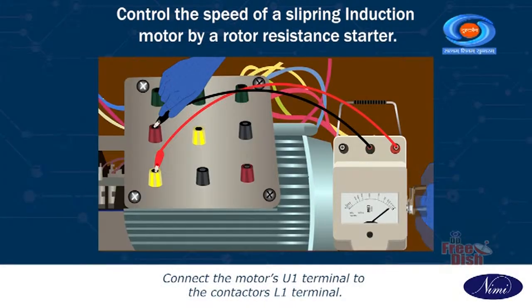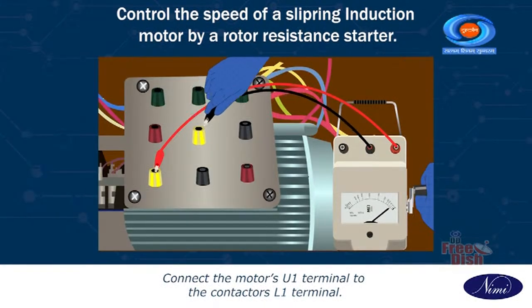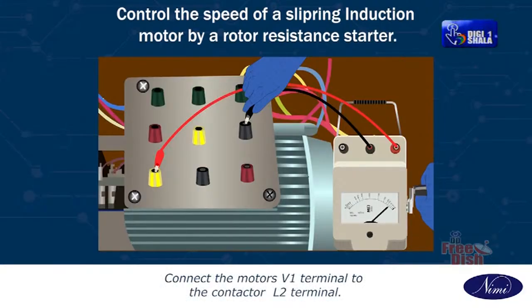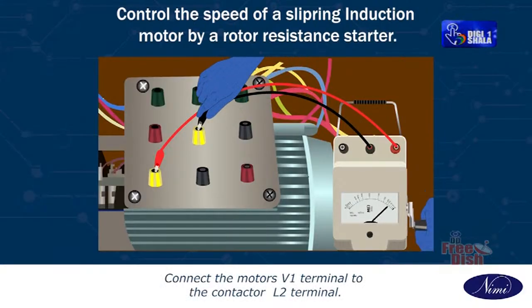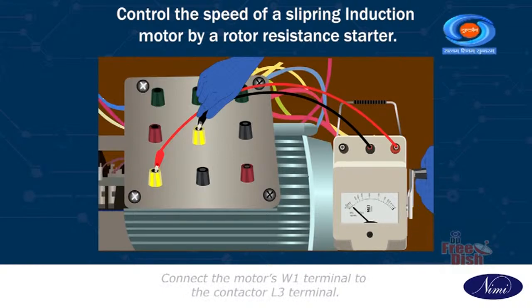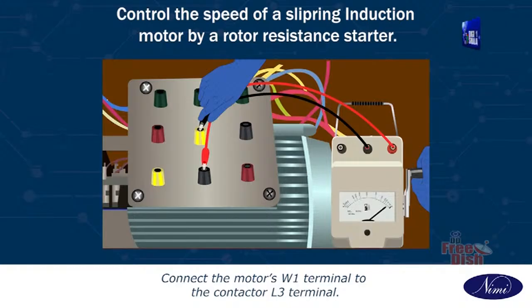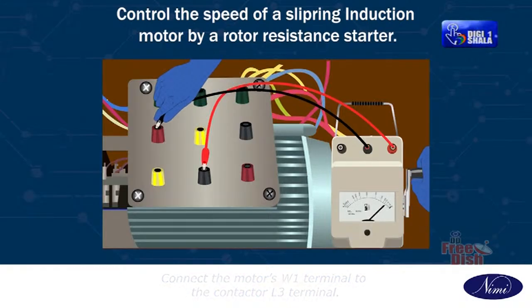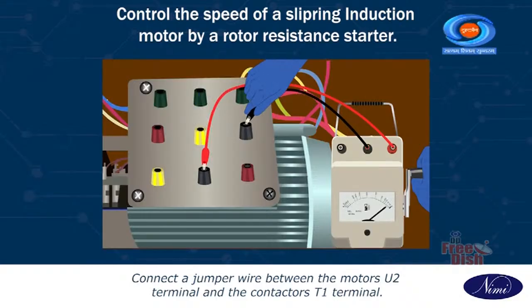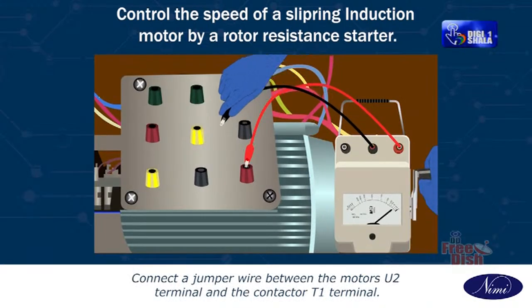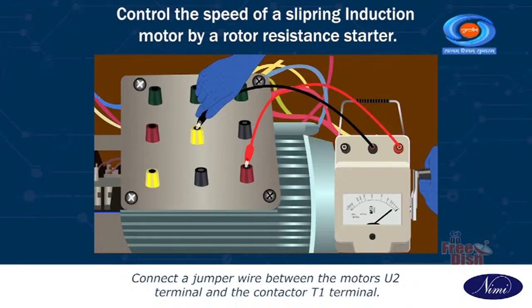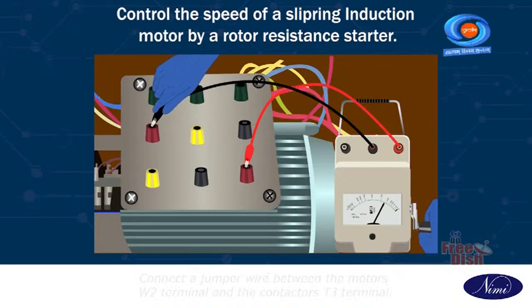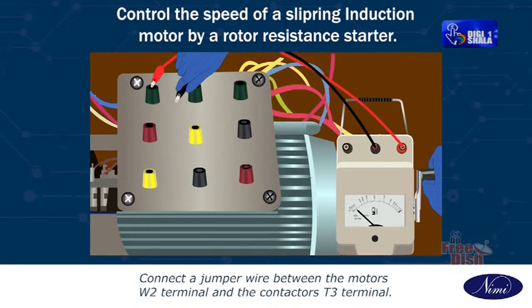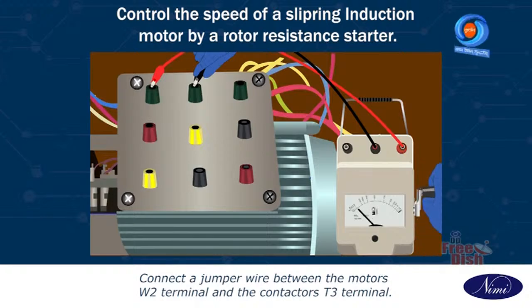Connect the motor's U1 terminal to the contactor's L1 terminal. Connect the motor's V1 terminal to the contactor's L2 terminal. Connect the motor's W1 terminal to the contactor's L3 terminal. Connect a jumper wire between the motor's U2 terminal and the contactor's T1 terminal. Connect a jumper wire between the motor's V2 terminal and the contactor's T2 terminal. Connect a jumper wire between the motor's W2 terminal and the contactor's T3 terminal.